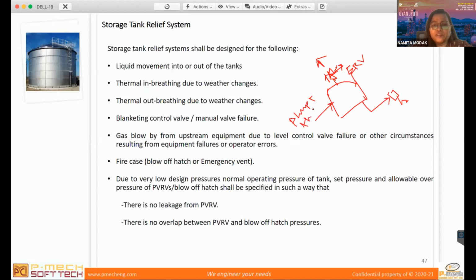So API 2000 is used for the venting calculation of storage tanks. So here you estimate this out-breathing flow rate, and similarly for the in-breathing flow rate, your pump in flow rate plus the thermal effect. So that will give you the out-breathing flow rate. And the emergency relief valve is something you use only for fire. So whenever a fire happens, in API 2000, all the detailed calculations are provided on how to estimate the fire load.